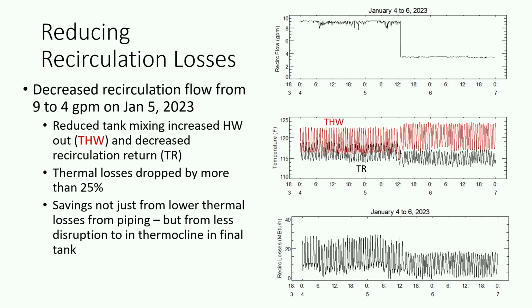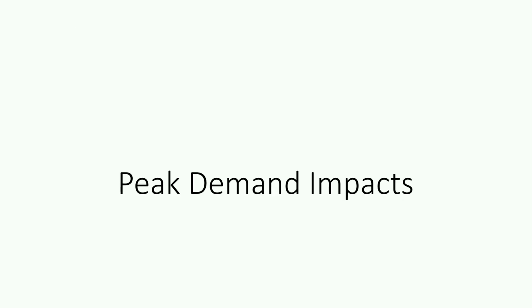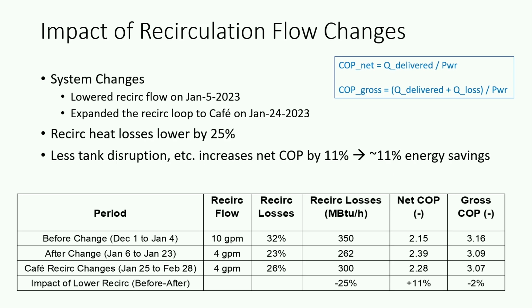And so one thing we did is we made this change, we lowered the recirculation flow, and what we saw is the delivered hot water temperature jumped up, the recirculation temperature went down, not a lot, and we saw the recirculation heating losses change too. When we look at this period, it turns out other things were happening in the building, but we were able to compare a few days, and the recirculation losses were 32%. After we lowered the GPM, they became 23%. And the gross COP is the far column. That really didn't change because the heat pump is a different load, but it's still the same efficiency.